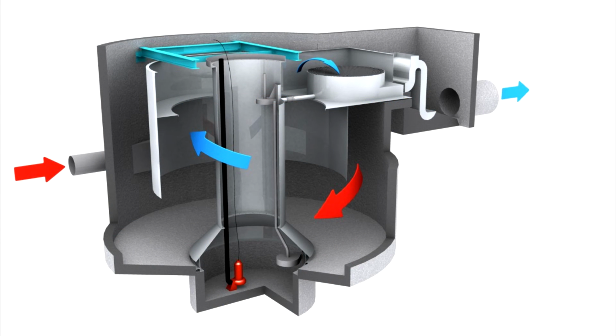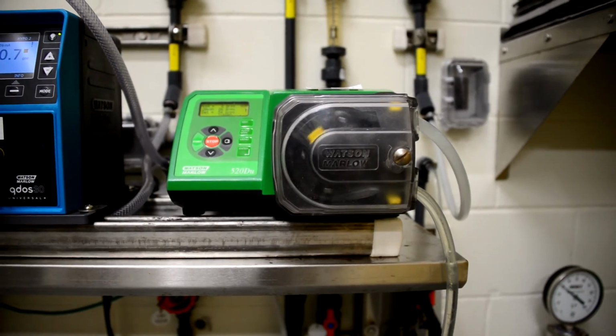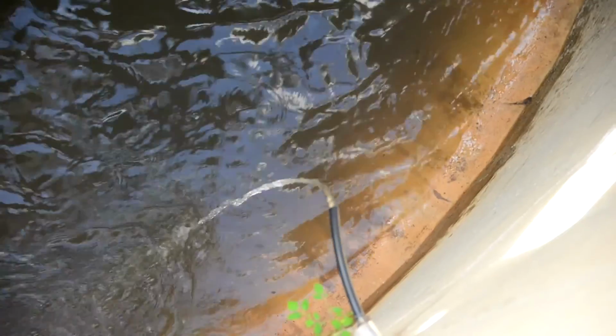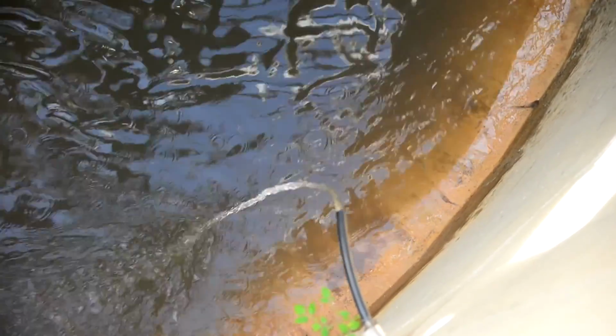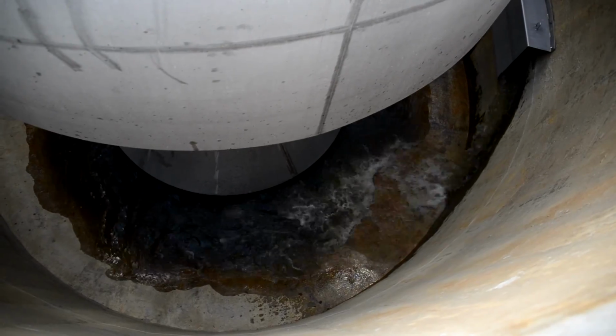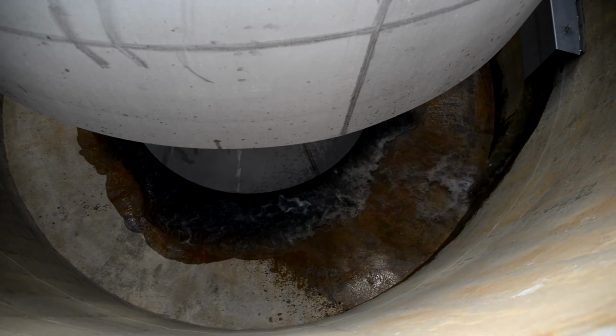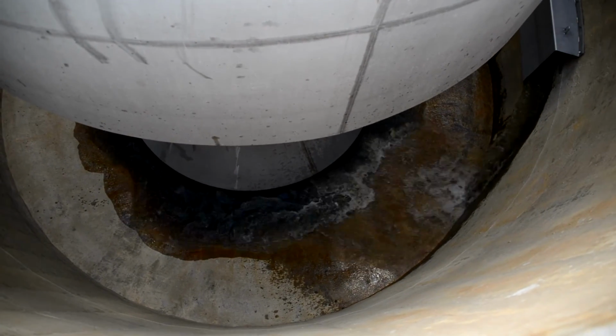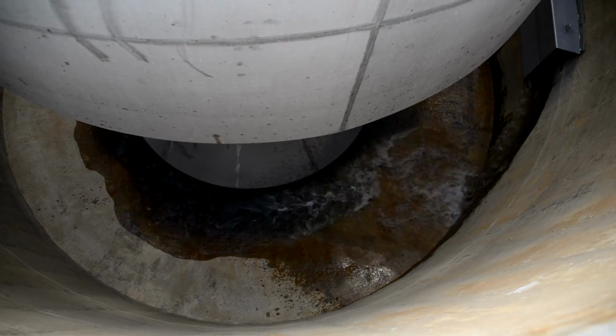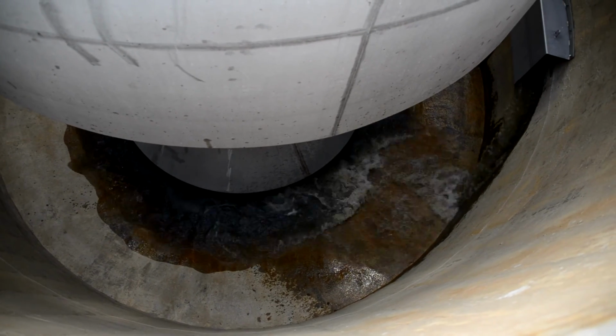Once flow is diverted to the Storm King at the diversion structure, aka grassy knoll, the stormwater influent sampler begins taking samples, and sodium hypochlorite begins pumping to the Storm King. Flow enters the Storm King tangentially into the side of the cylinder so that the contents rotate gently about the vertical axis. Flow first spirals down the perimeter to allow particles to settle out by gravity.